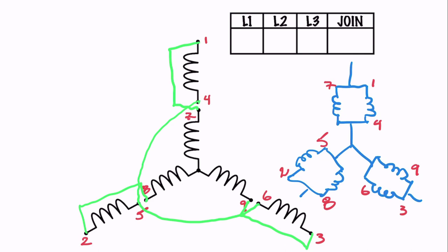So drawing it out: we have one and seven, two and eight, three and nine across there. Then we connect four, five, and six together — that's the joining point. That gives us the lower voltage connection because the windings are in parallel. Voltages in parallel stay the same. Line one connects to one and seven, line two connects to two and eight, line three connects to three and nine. Then four, five, and six are joined together. That's the hardest part of the Y connection — making sure you understand the parallel connection.